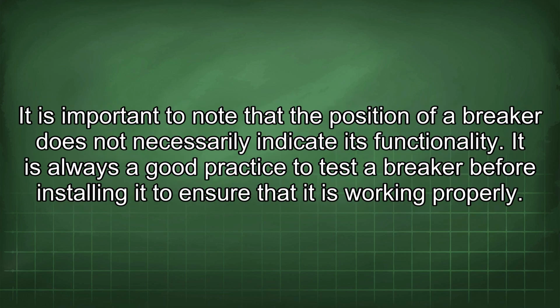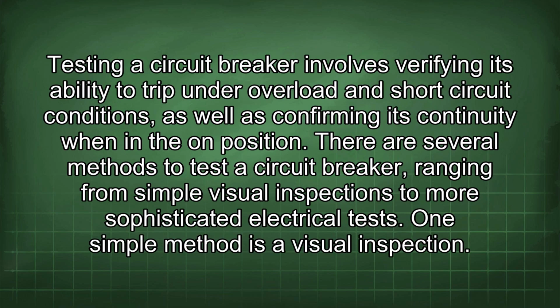It is important to note that the position of a breaker does not necessarily indicate its functionality. It is always a good practice to test a breaker before installing it to ensure that it is working properly. Testing a circuit breaker involves verifying its ability to trip under overload and short circuit conditions, as well as confirming its continuity when in the on position. There are several methods to test a circuit breaker, ranging from simple visual inspections to more sophisticated electrical tests.